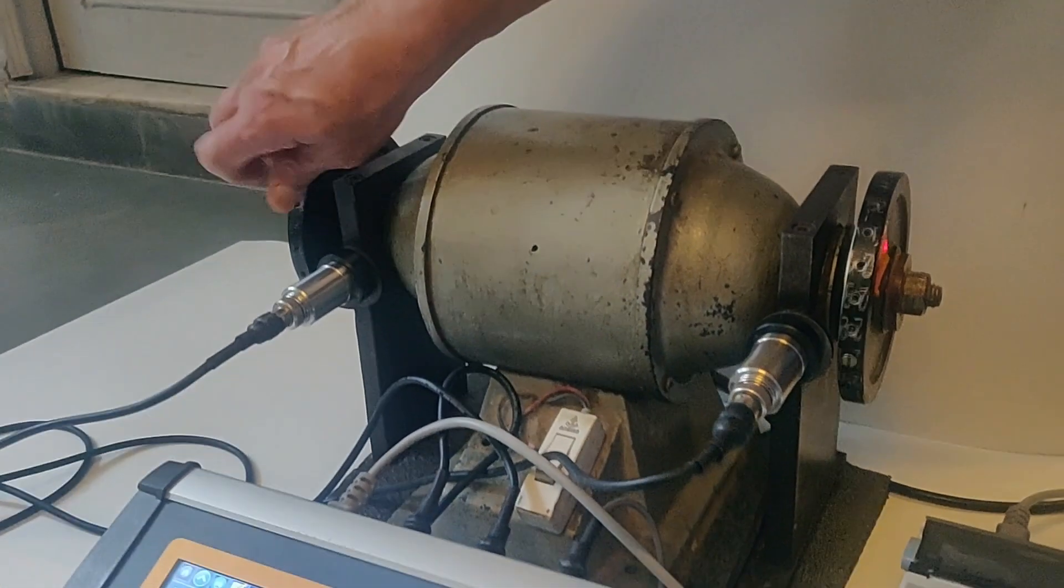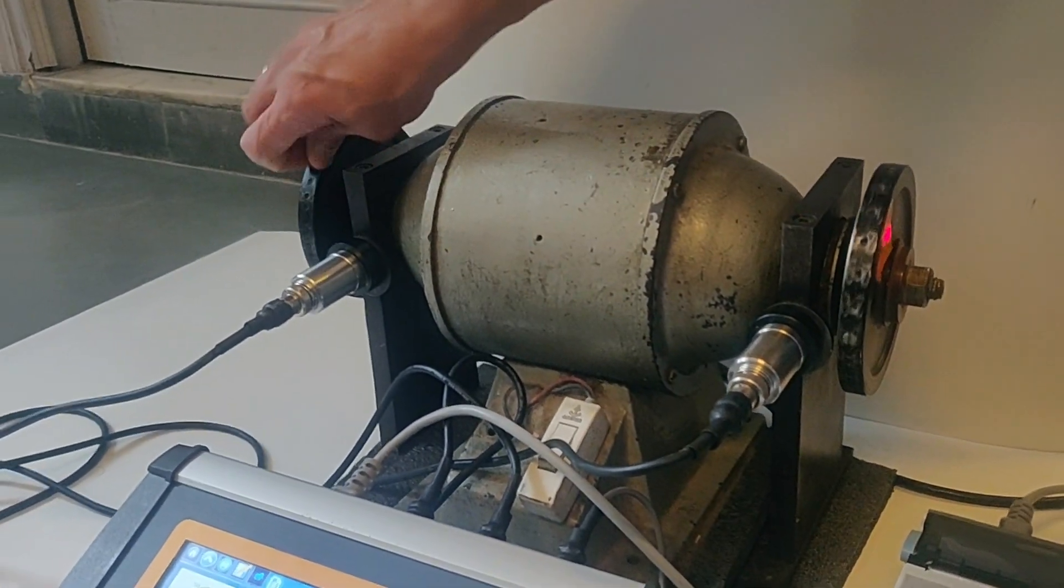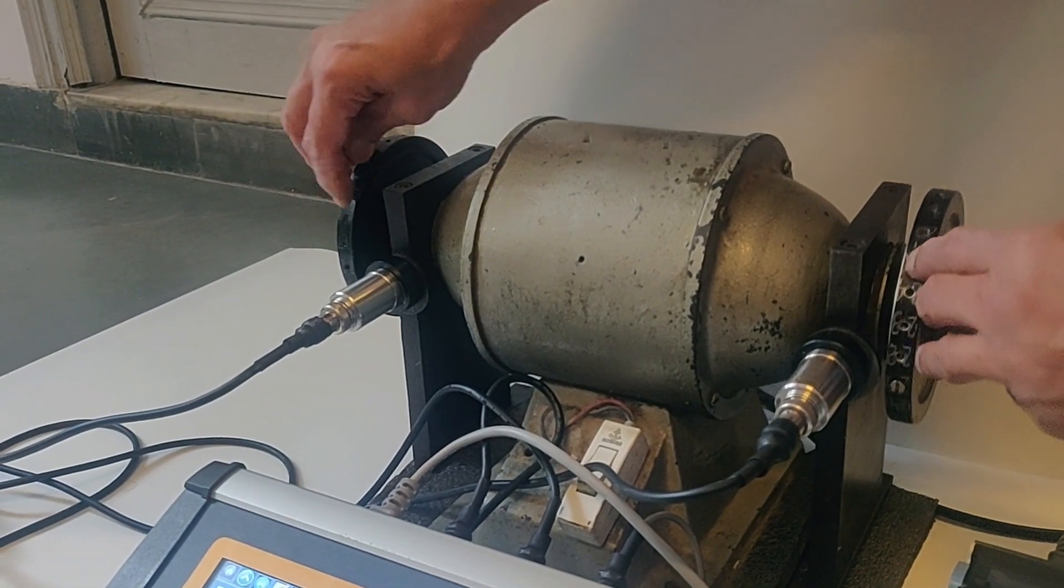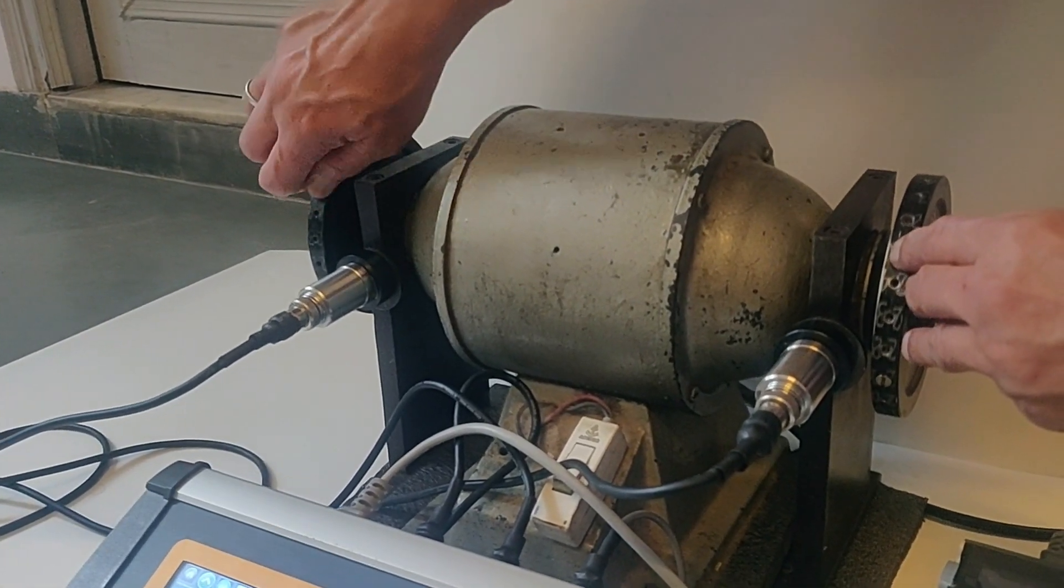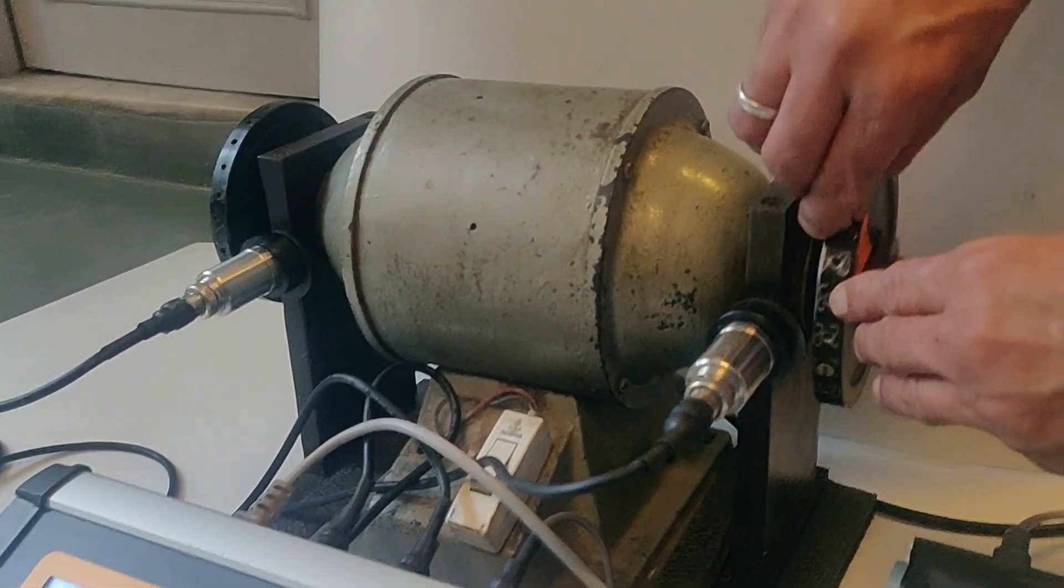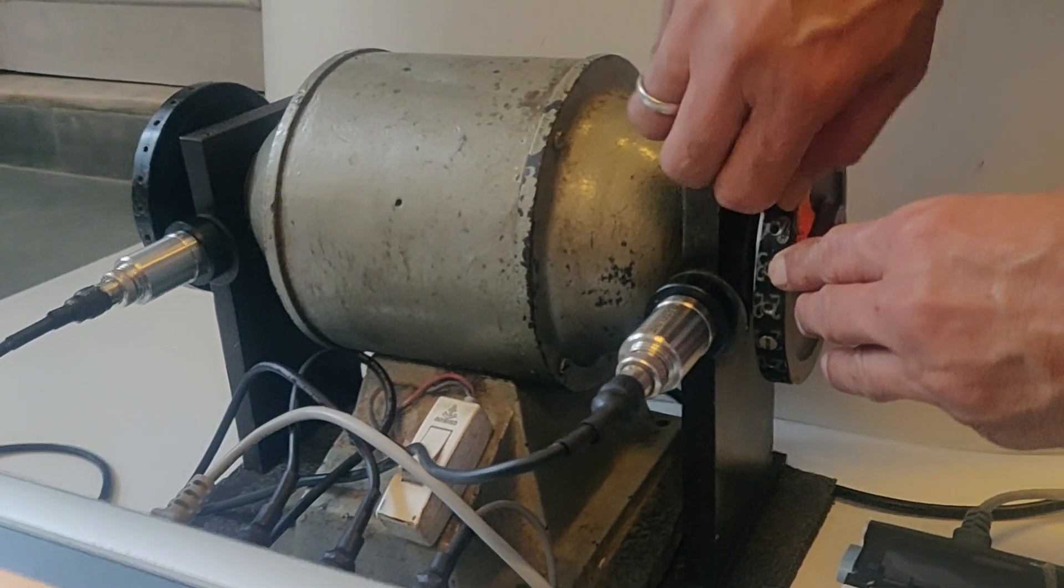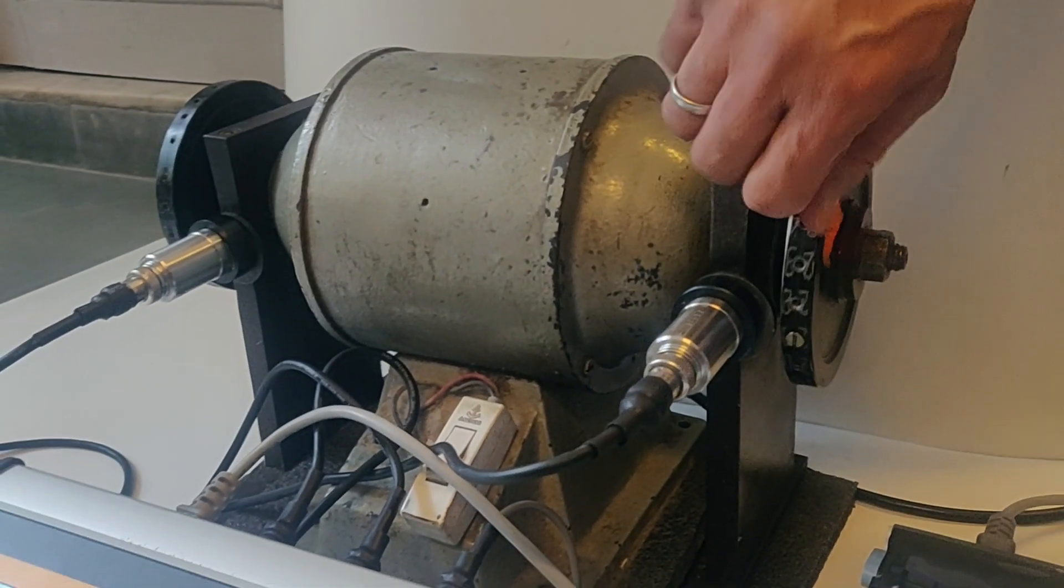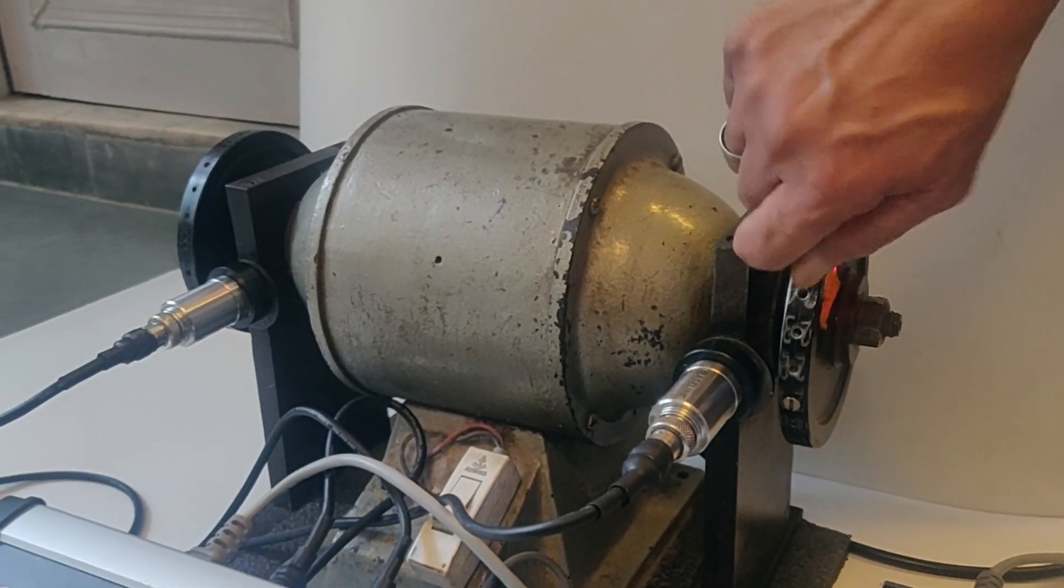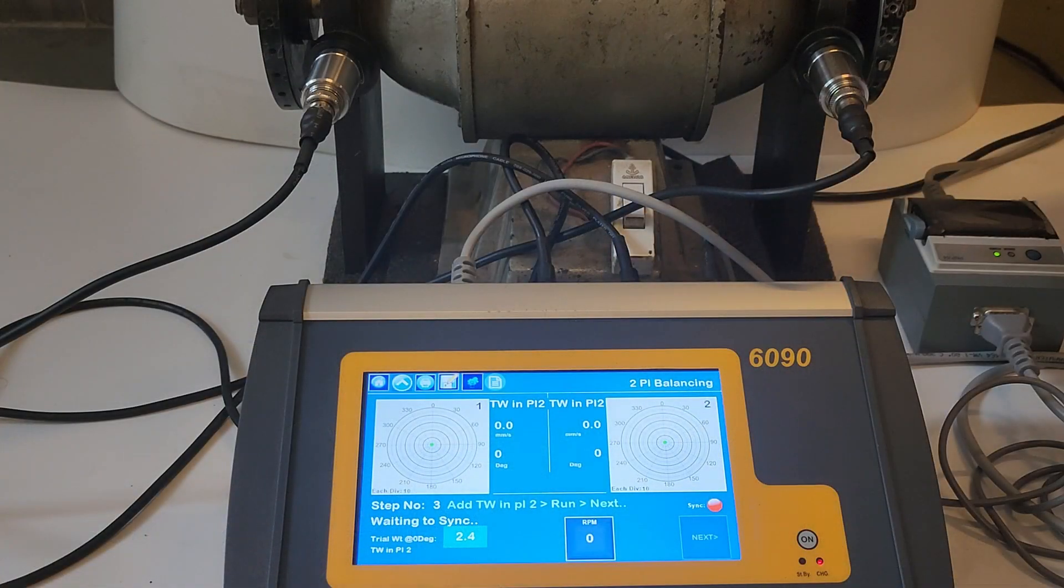Step number three is to remove the trial weight from plane one and add the same trial weight to plane two. After that start the rotor, press next, and stop the rotor. The final result will be displayed on the screen after the rotor is stopped.